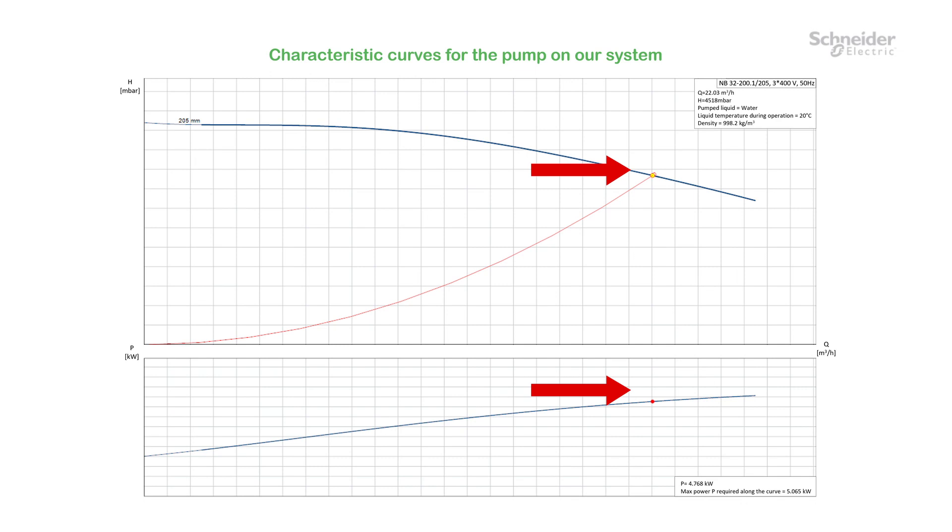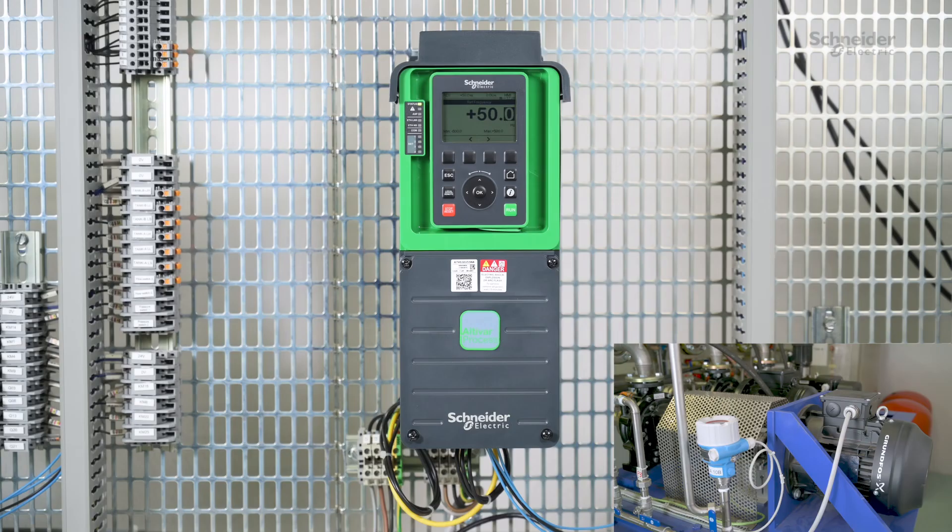You can find the coordinates of the BEP on the data sheet of the pump. The ATV600 will monitor where the actual operating point of the pump and associated motor is relative to the BEP through pump characteristics curves.